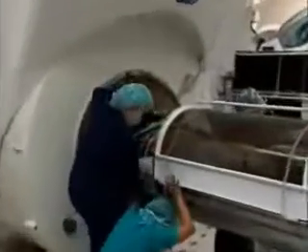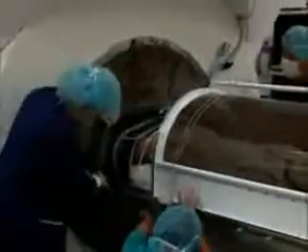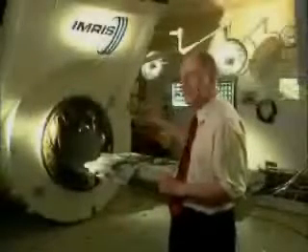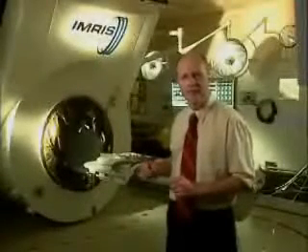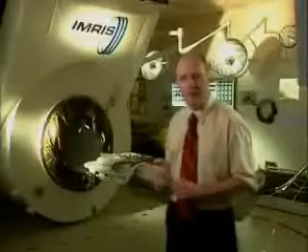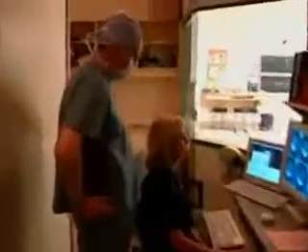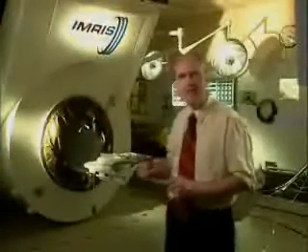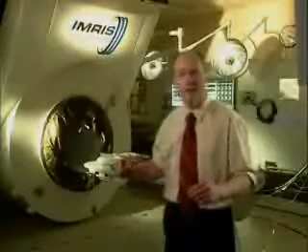The root of this innovation is that we have placed a high-field MRI instrument in an operating room. You see that instrument with the large bore in it is a magnet. That magnet is a high-field superconducting magnet that allows surgeons to obtain the images before, during, or after surgery. The other thing you see is an OR table. That is not a normal operating room table. That is a table that can go inside a magnet and not get stuck.